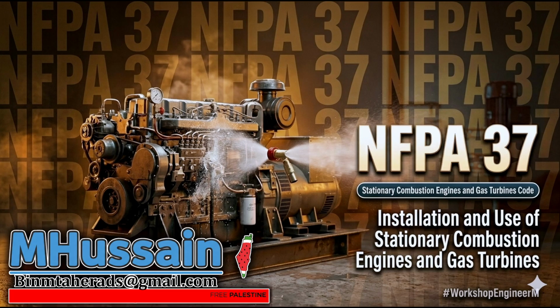That's why the standard is Schedule 40 black iron pipe. With welded or threaded joints. Because iron will survive the initial fire long enough for the suppression system to kick in. Exactly. The only exception is a specialized listed vibration connector right where the rigid pipe meets the vibrating engine block. Now, diesel behaves like a liquid. It pools, it drops. But what about gaseous fuels? Gases require a totally different strategy.